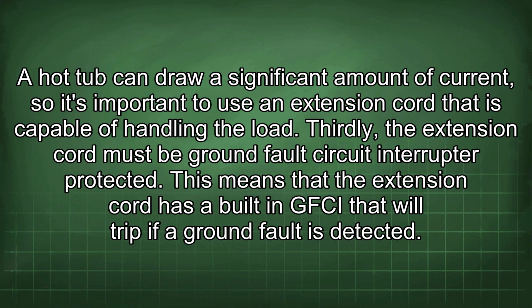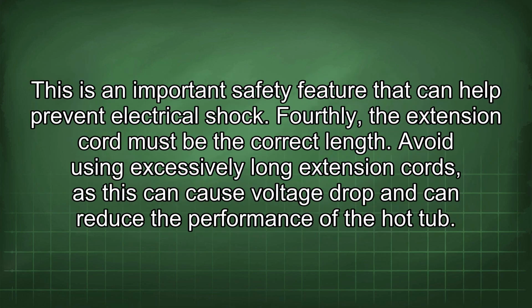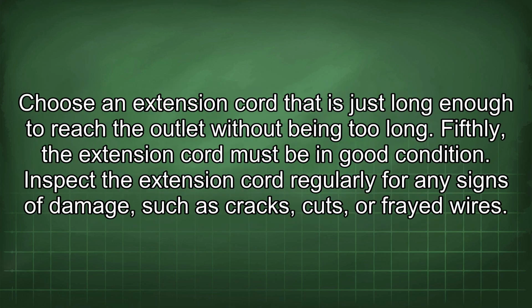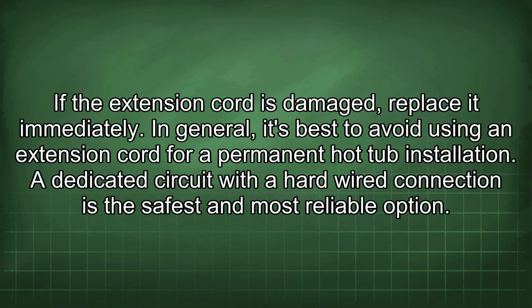Thirdly, the extension cord must be ground fault circuit interrupter protected. This means that the extension cord has a built-in GFCI that will trip if a ground fault is detected. This is an important safety feature that can help prevent electrical shock. Fourthly, the extension cord must be the correct length. Avoid using excessively long extension cords, as this can cause voltage drop and can reduce the performance of the hot tub. Choose an extension cord that is just long enough to reach the outlet without being too long. Fifthly, the extension cord must be in good condition. Inspect the extension cord regularly for any signs of damage, such as cracks, cuts, or frayed wires. If the extension cord is damaged, replace it immediately.